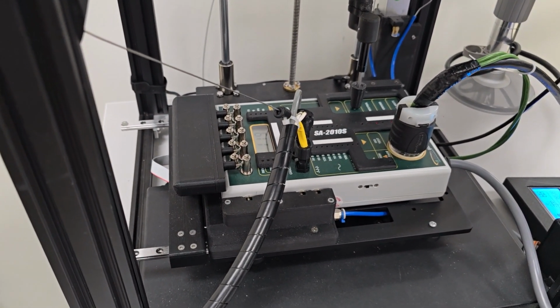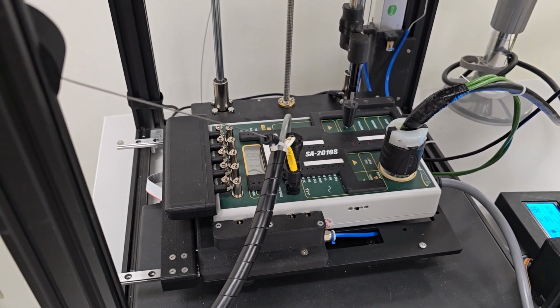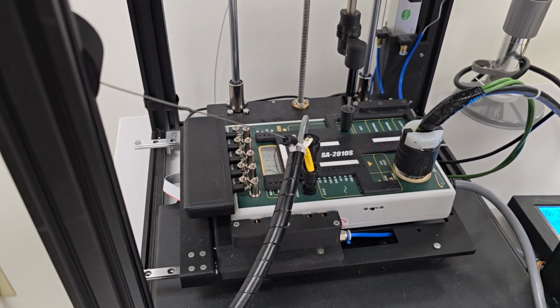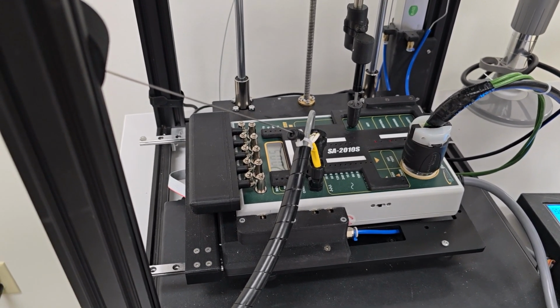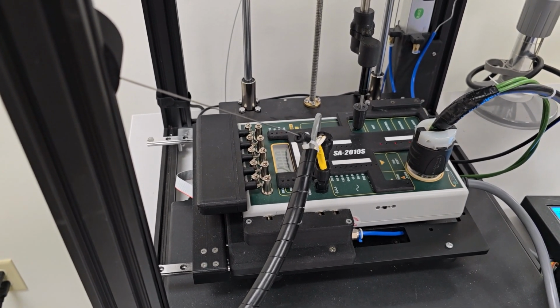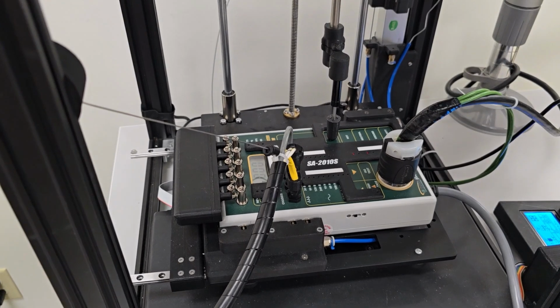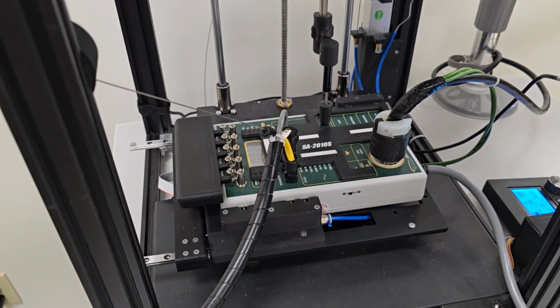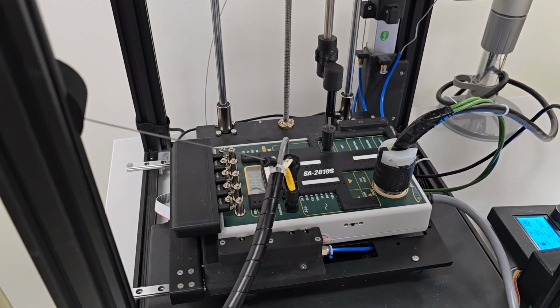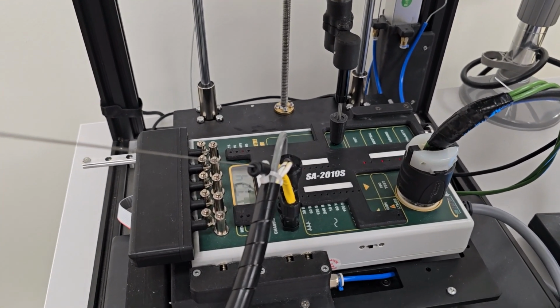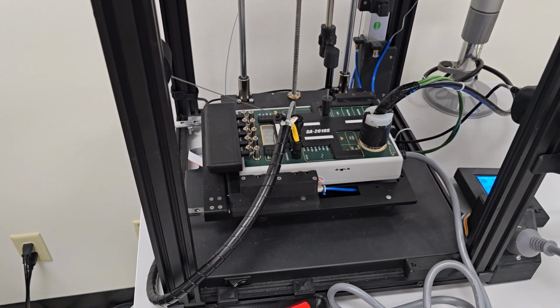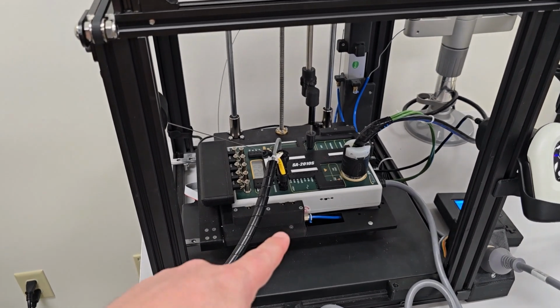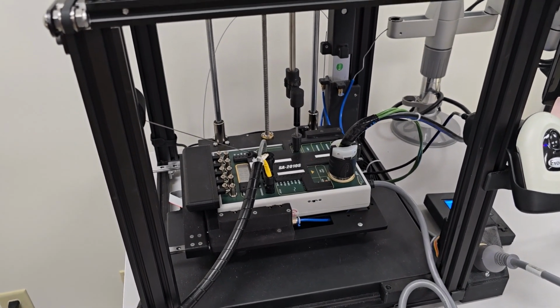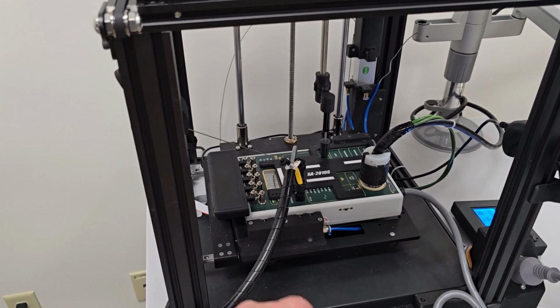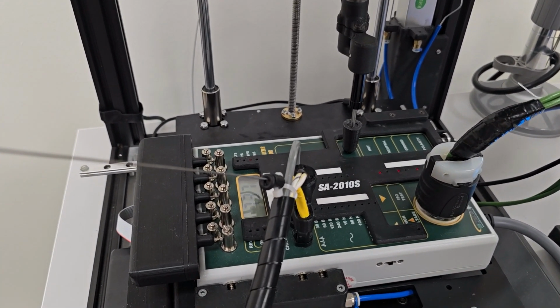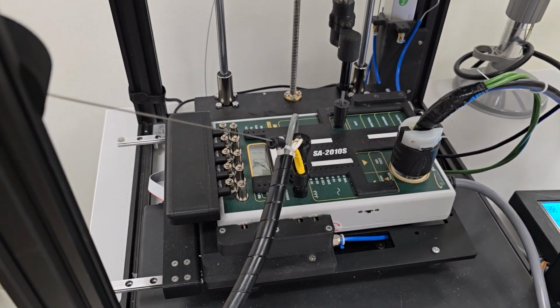Oh, that's cool. So this is a way that we can automate our routine calibrations of safety analyzers. Right. And then we can pass that savings on to you, because rather than having a person sitting here pushing these buttons, we can just have the machine do it over and over again. It gives us repeatability, and you make sure you don't fat finger any numbers that you're typing in. Yeah. Another interesting thing, especially with the membrane buttons, is if it doesn't activate, then we as humans would tend to just hit it harder. But with the machine, if it doesn't activate, now you know that there's a problem with the membrane button, something that a human might not be able to detect, because we would just naturally push it harder. So you have a pre-configured X and Y axis, and then it presses it. That's very cool.